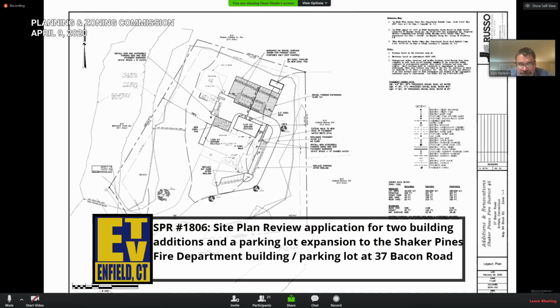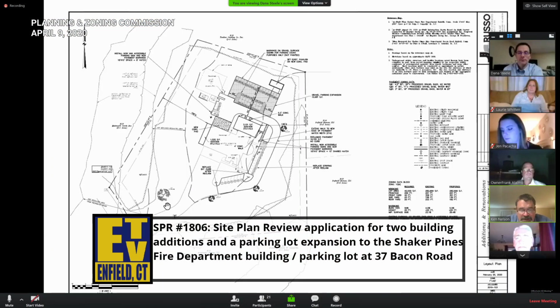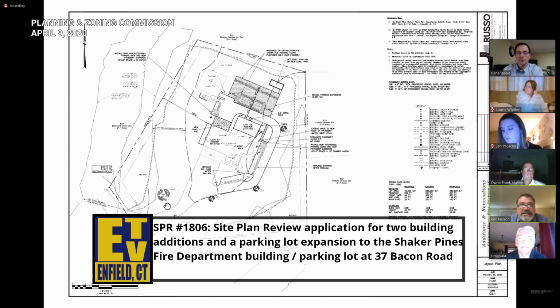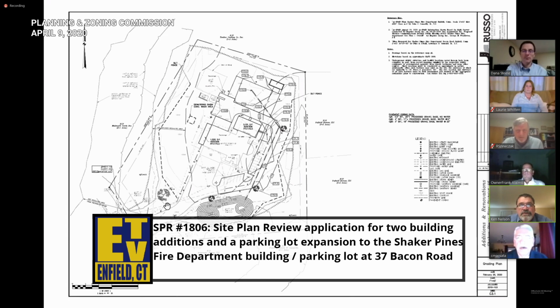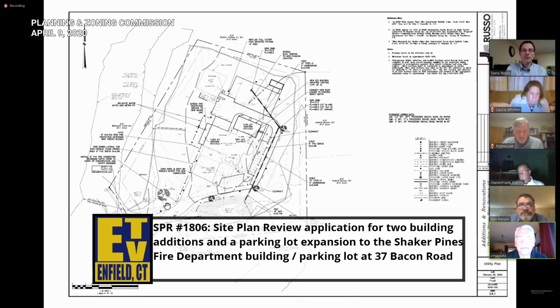Okay, I have several concerns. The fire equipment itself, where is it cleaned? It's washed usually inside the bay. Okay, do the parking lot drains go through the oil separator? The only parking lot drains are out away from the bays, about halfway down the driveway. No, they don't go through the separator. The separator is only for what goes to the sanitary sewer.